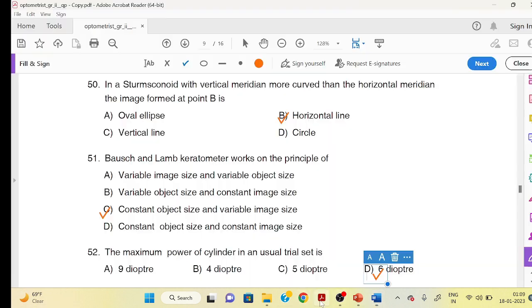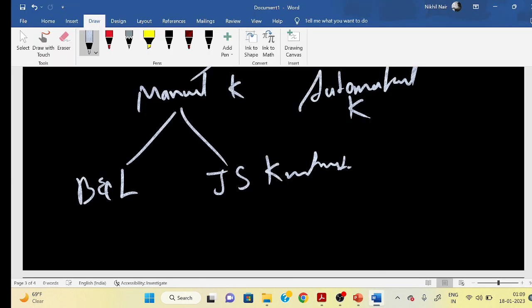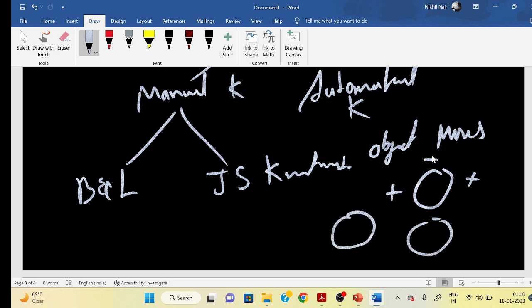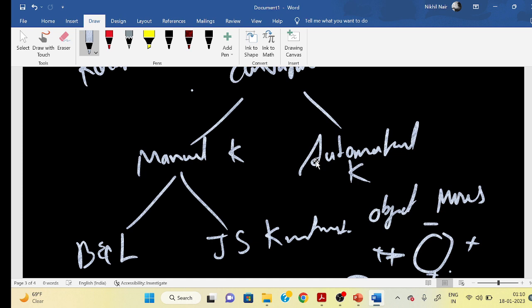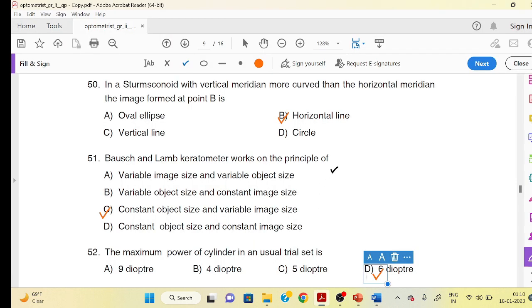The basic principle of the keratometer is constant object size and variable image size. In Javal's type, there is constant image size with variable object size. You can use a double prism on two sides — one with a minus sign and one with a plus sign — to align the mires.